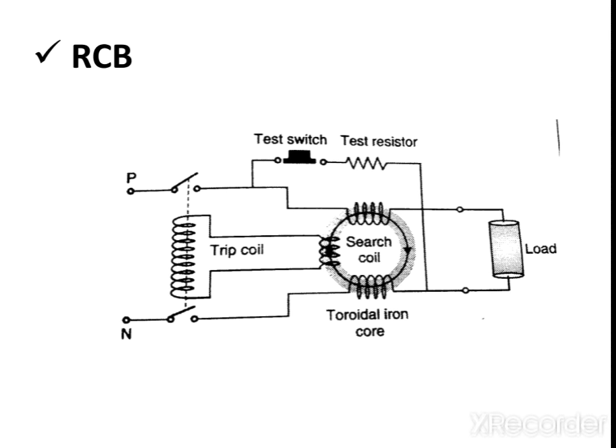The next type of protective device is RCB. RCB means residual current breaker. RCB works on the assumption that the current going to the electronic circuit or electronic devices must come out from the neutral wire. If there is no other way for current flow, then the RCB measures the current going inside the load equipment and coming out from the load equipment. If both currents are the same, then there will be no problem, and this condition is normal functionality of the equipment. This device is also called RCCB, meaning residual current circuit breaker.